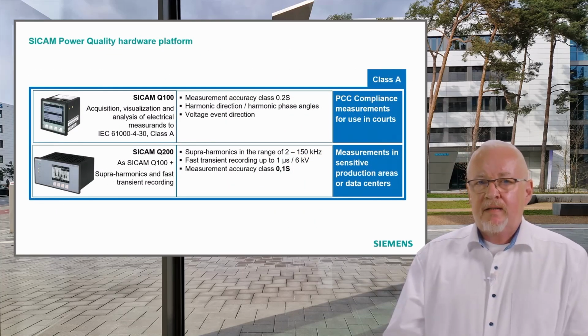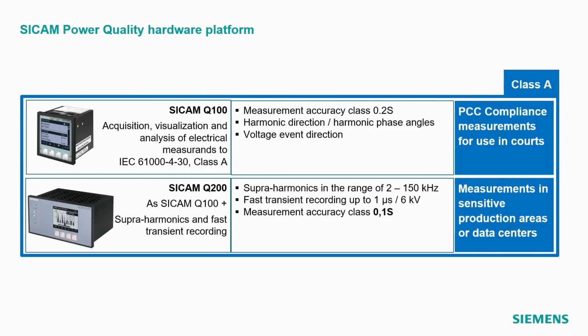Here we have our 2 devices. SICAM Q100 offers acquisition, visualization, and analysis of electrical measurements according to IEC 61000-4-30 Class A. It has a measurement accuracy class 0.2S for current and power measurement. It offers harmonic direction and harmonic phase angles in addition to the standard, and also additional functions like voltage event detection indication. The Q100 is suitable for compliance measurements for use in courts. It's a good basic Class A measurement, but we offer some more in Q200.